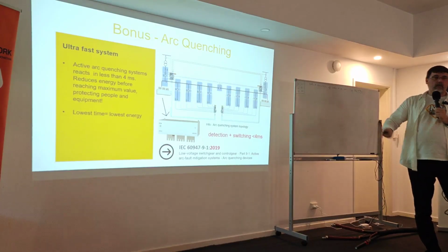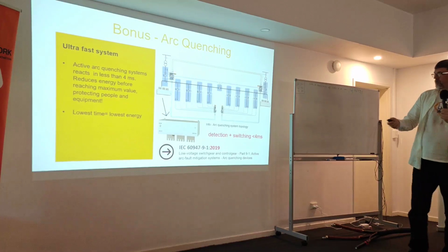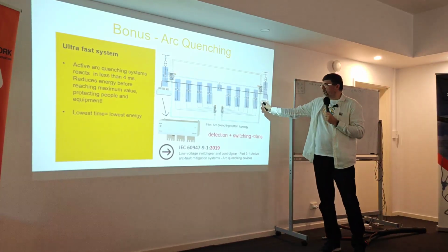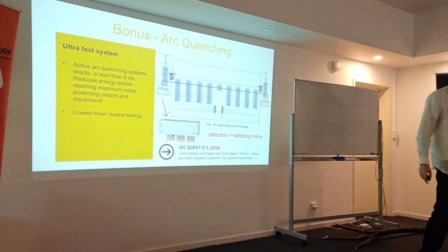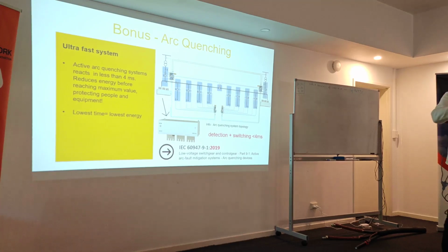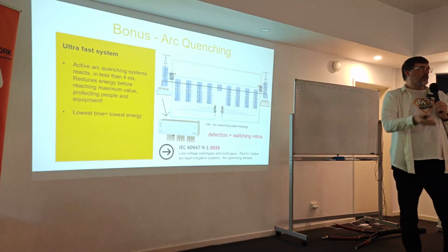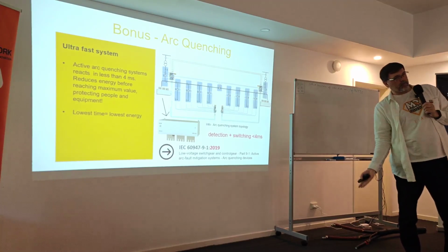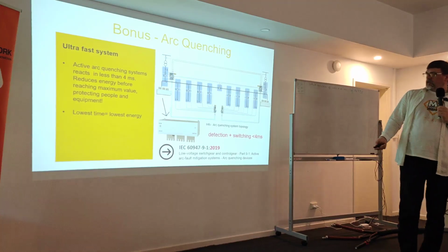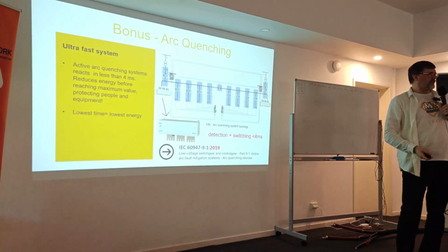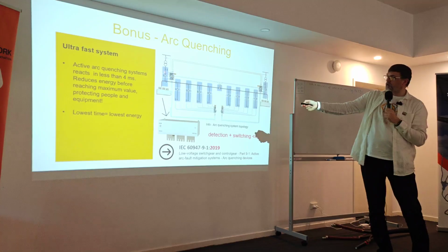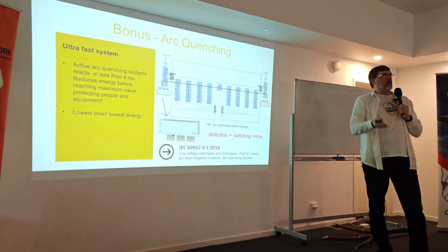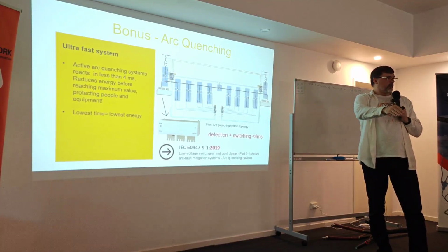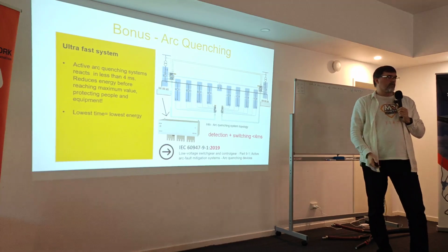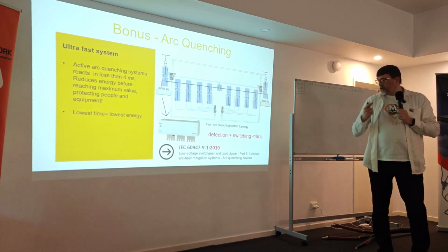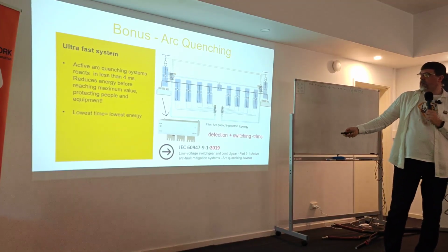And this is relatively cheap still. And the last thing was the thing that David was showing, the quencher. So I don't know if I have the same video from Miko. Quencher, if you don't know how it works, is a simple device. It creates a short circuit. If you create a short circuit in the system, at this point of the short circuit there is no voltage, or it is nearly zero. When there is no voltage for the arc, the arc disappears, it is extinguished. That's why they call it the quencher, the extinguishing system. It sounds weird because it sounds like a fire extinguisher, and it's not really what it does. Then you also have to send a signal to the breakers to trip, to open. Because we have a short circuit in the system, but a short circuit is something that devices are rated for. If we trip it in 100 milliseconds, perfect, because most of the things will be rated half a second, 1 second. They can withstand it. But arc flash will burn everything. Yeah, so this is how it works.